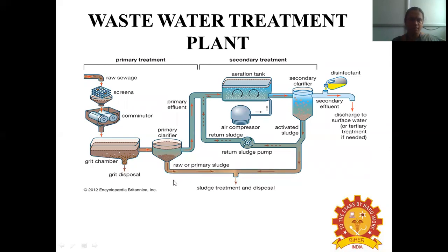Next comes the primary clarifier or primary sedimentation process. Water is allowed to stand so that all suspended solids are brought down by the force of gravity. This settled matter is called primary sludge. The clarified water at the top layers is pumped to the secondary clarification process. The primary sludge is disposed of by sludge treatment.